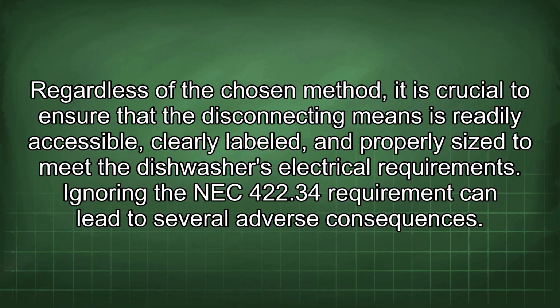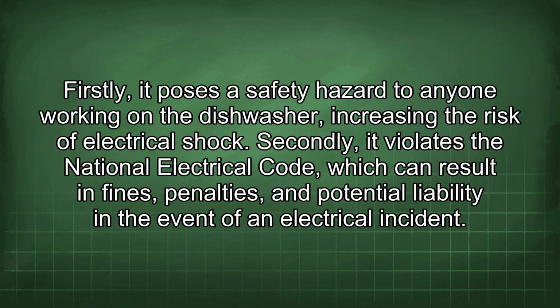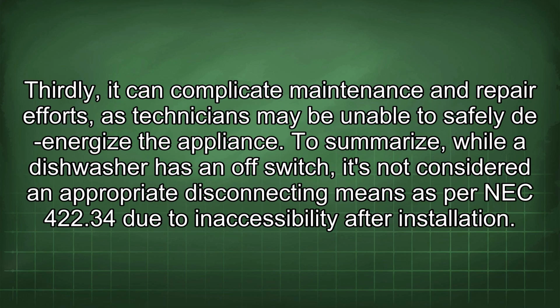Ignoring the NEC 422.34 requirement can lead to several adverse consequences. Firstly, it poses a safety hazard to anyone working on the dishwasher, increasing the risk of electrical shock. Secondly, it violates the National Electrical Code, which can result in fines, penalties, and potential liability in the event of an electrical incident. Thirdly, it can complicate maintenance and repair efforts, as technicians may be unable to safely de-energize the appliance.